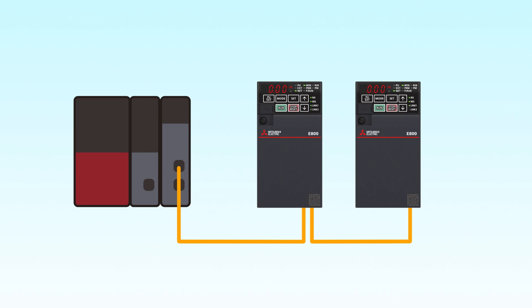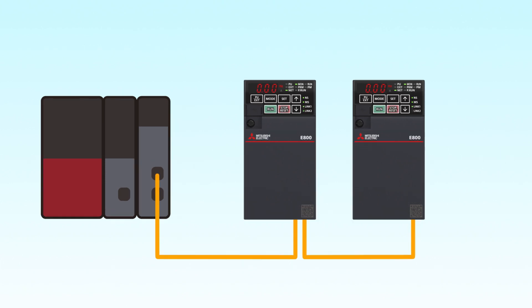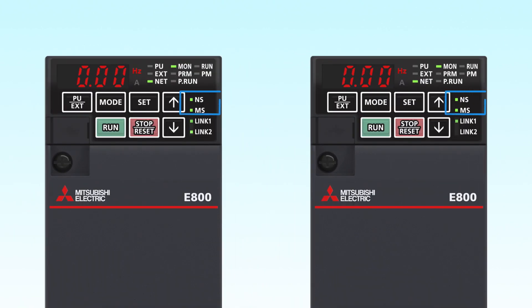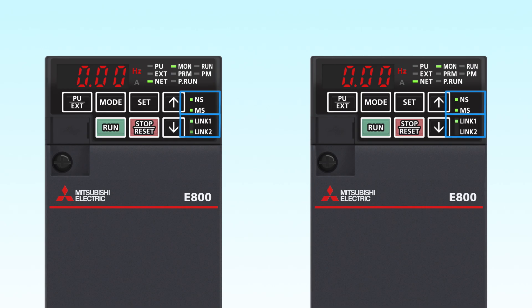After the writing has been done, check the inverter's LEDs. CC-Link IE-TSN communication has been successfully established when the NS and MS LEDs constantly display green, and the Link 1 or Link 2 LED is flashing green.